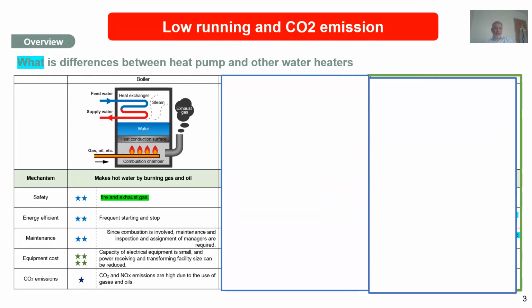What are the advantages and considerations of using those systems? First, since we are using gas to heat the water, there is a fire and exhaust gas. We need to maintain those things, so that's a safety consideration. Efficiency: since gas heating is not the most efficient, the max you can do is 100% efficiency, and it cycles on and off depending on the load. If you want to give a rating for efficiency, you end up with a two-star rating.